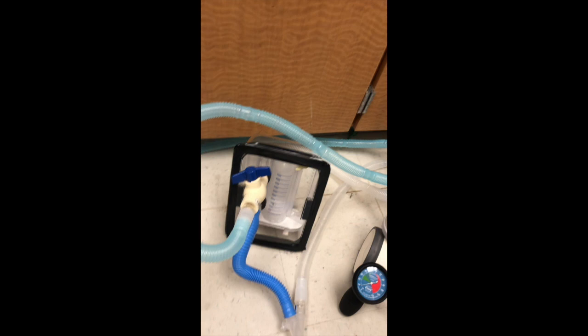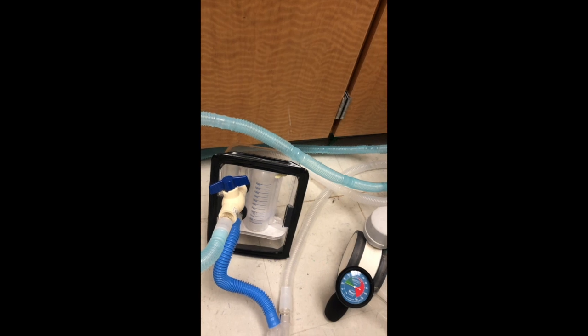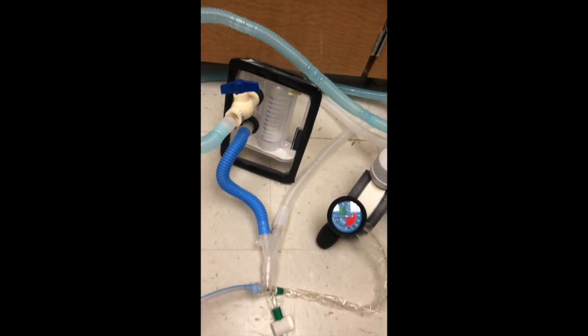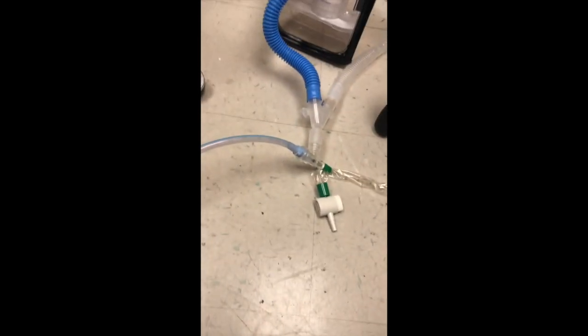inspiratory limb. So if you look at the inspiratory limb, it's connected to this ball valve, which is very important and is a key component for the individual ventilatory needs of a patient and to maintain or change pressure or volume. This is connected to the box in an airtight manner, and inside it just opens into the box. The tubing of the spirometer is connected outside in an airtight manner to the artificial lung, and the adapters are similar to the adapters in the ventilator, so it's easy to put the adapters in. It just has to be done in an airtight manner.